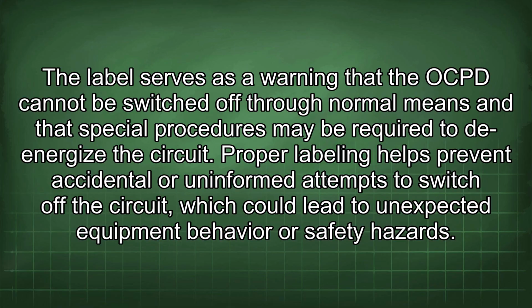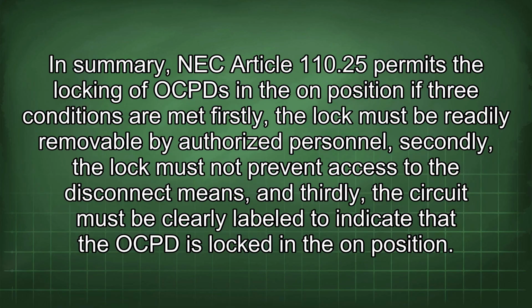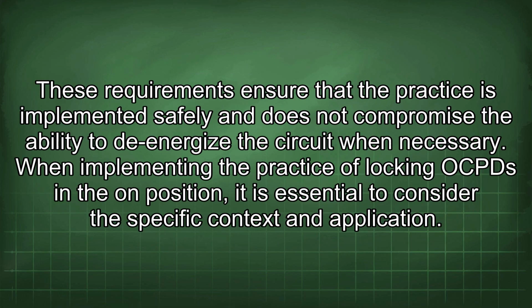Proper labeling helps prevent accidental or uninformed attempts to switch off the circuit, which could lead to unexpected equipment behavior or safety hazards. In summary, NEC Article 110.25 permits the locking of OCPDs in the on position if three conditions are met. Firstly, the lock must be readily removable by authorized personnel. Secondly, the lock must not prevent access to the disconnect means. And thirdly, the circuit must be clearly labeled to indicate that the OCPD is locked in the on position.